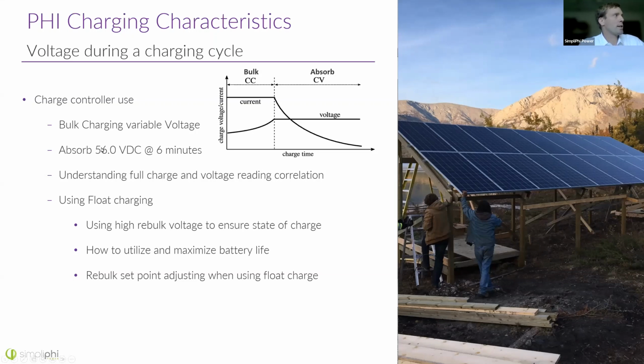Once the charger reaches 56 volts DC, then we enter the absorb cycle, and this is a constant voltage. So we want to hold the charger at 56 volts, and the duration here is just 6 minutes. And that should top the battery off pretty close to 100% state of charge.